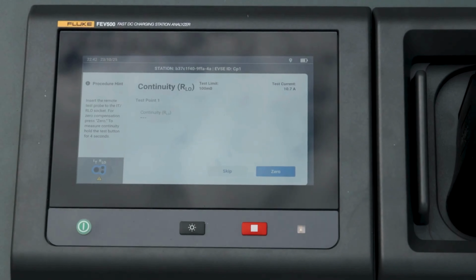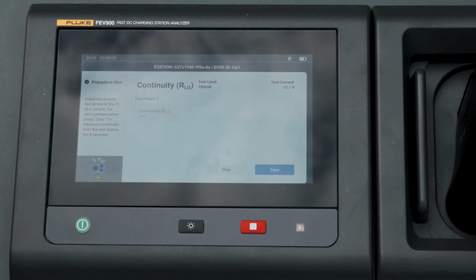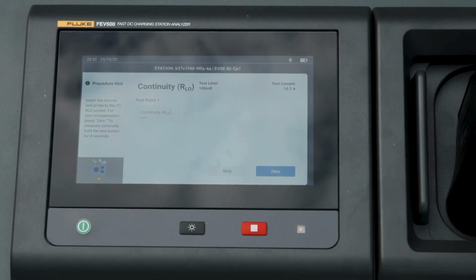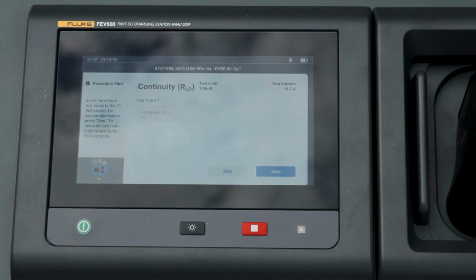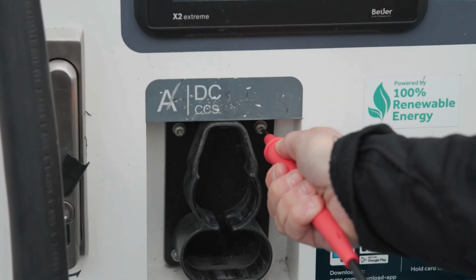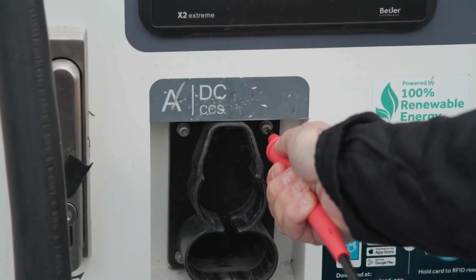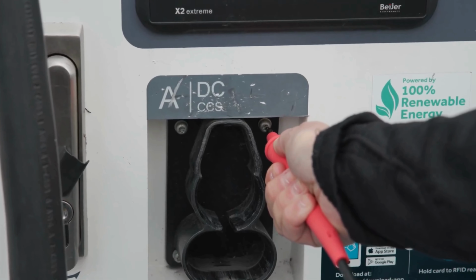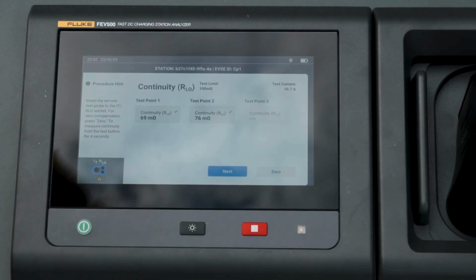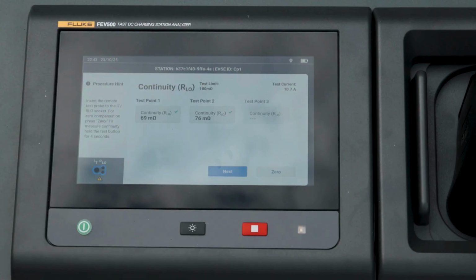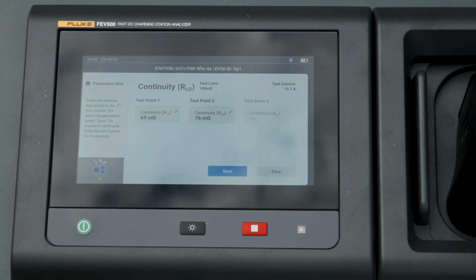Okay, now that we have zeroed out our test lead, I'm going to connect the test probe to the different metal housing points of the charging station to take my continuity measurements. Okay, now that I have taken my continuity measurements, and you can see you're able to take multiple measurements, up to 10 test points can be added. I'm going to press next.